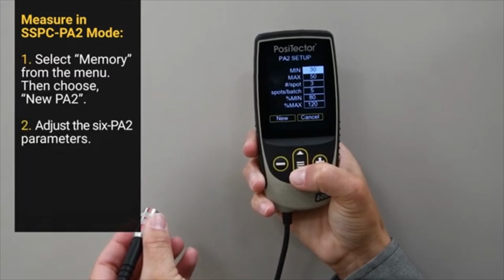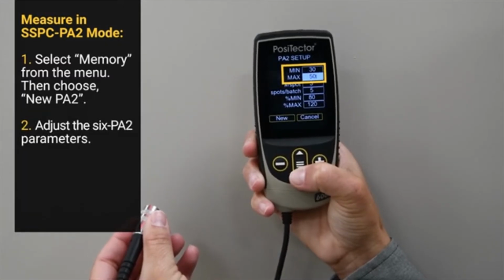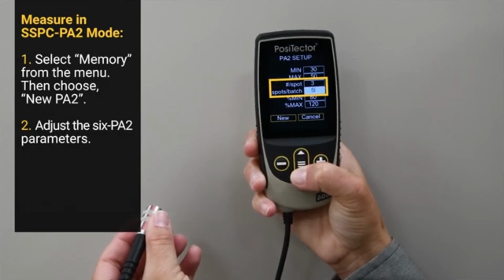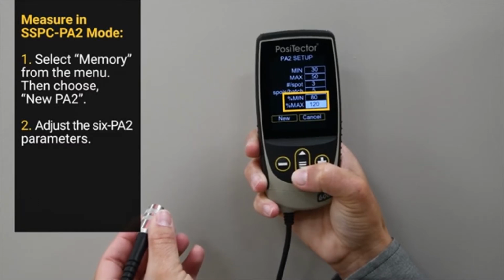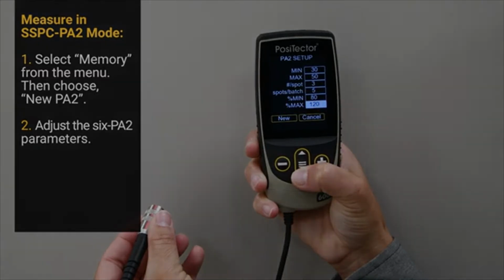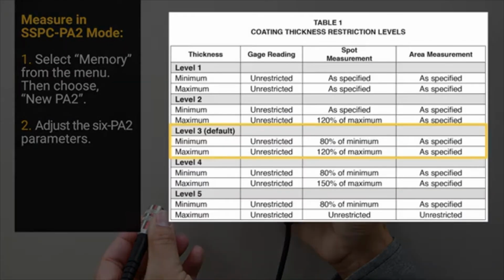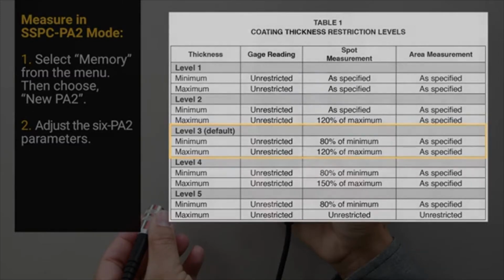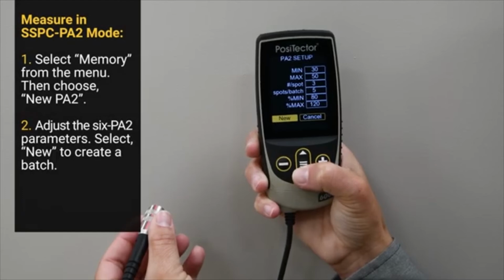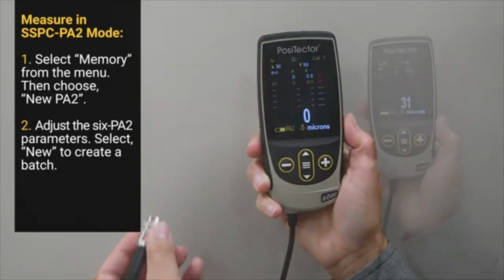6 parameters are displayed. The minimum and maximum coating thickness should be set according to project specifications. The number of readings per spot and the number of spots per batch default to 3 and 5 respectively, as specified in SSPC-PA2. The % minimum and % maximum options determine the allowable limits for each spot reading and are preset to the default Level 3 restriction level, but can be modified according to project specifications in Table 1 of SSPC-PA2. Once all of the parameters are set, select New to create a batch.